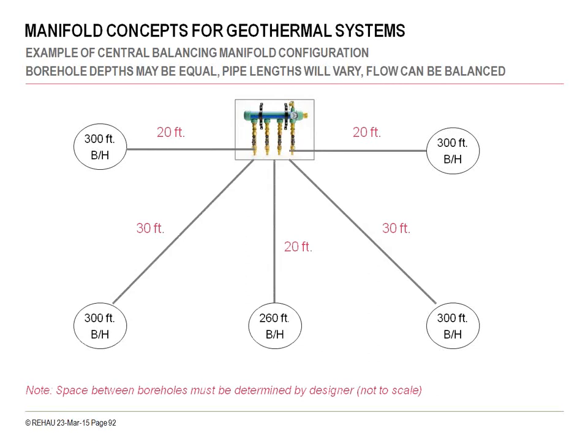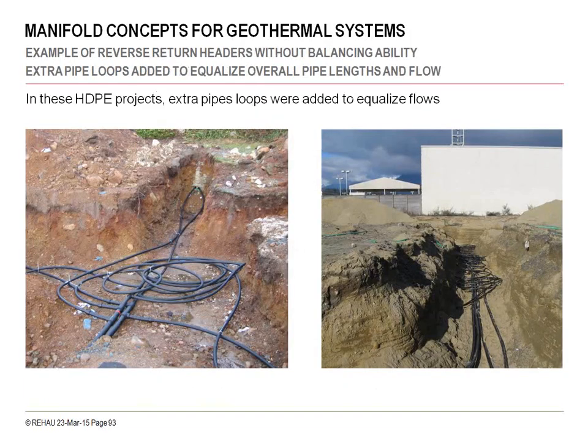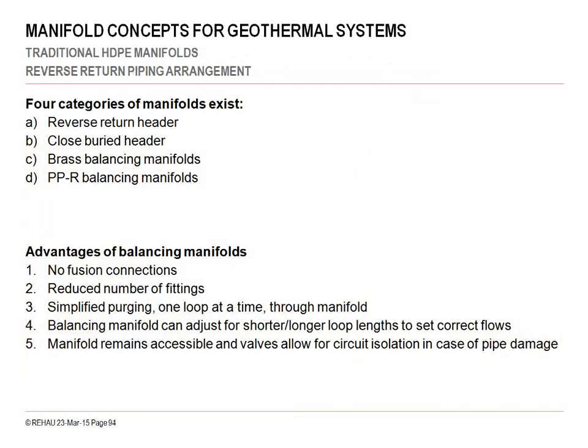In this case, you can see there's some different borehole lengths, 260 feet. Might have run into a problem, possibly a lot of water. So you do have the flexibility of being able to shorten one borehole and put possibly some additional borehole length to one of the other boreholes. This is just showing you an HDPE application where a bunch of additional pipe was thrown in to equalize the pipe lengths that I mentioned, to eliminate or prevent the short circuiting of the flow between the boreholes in the circuit.